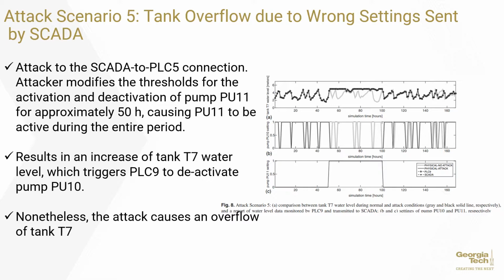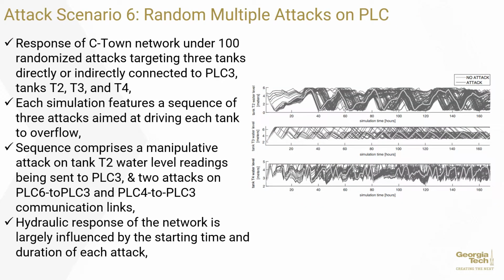This is again the tank 7 water level, pump 10 performance, and pump 11 performance versus time. And as we can see, there is a significant difference between the normal condition and the attack condition. Specifically, the pumps act completely differently. That may cause a lot of energy consumption versus the normal condition.